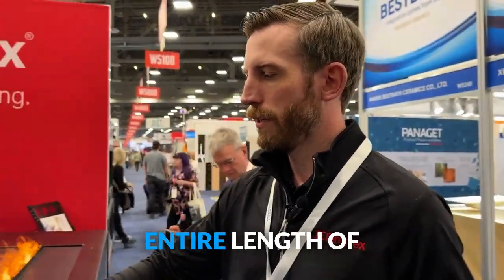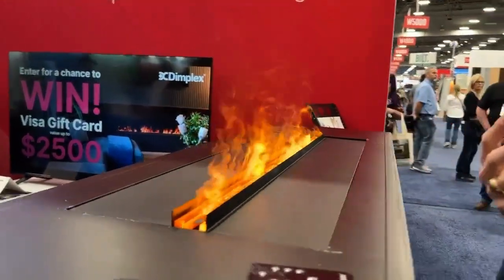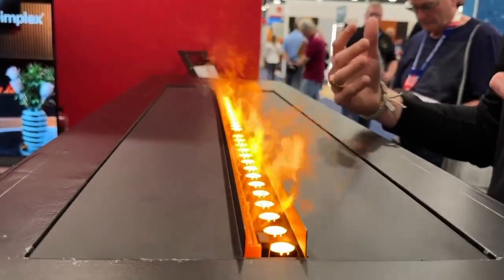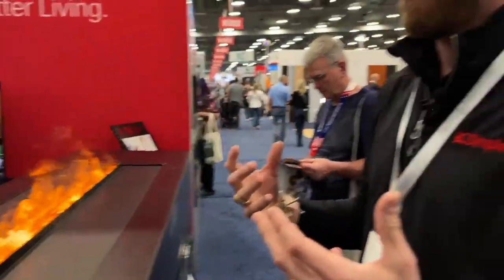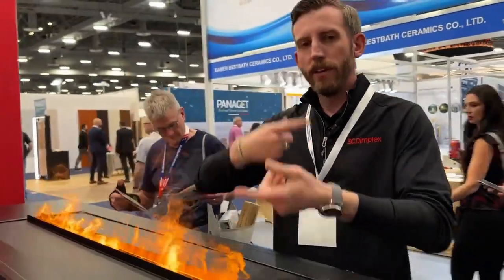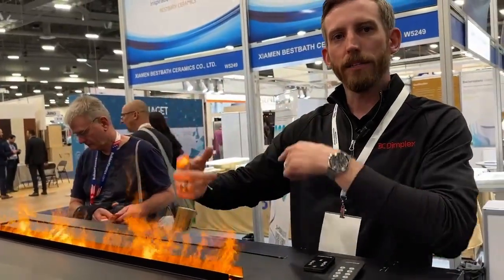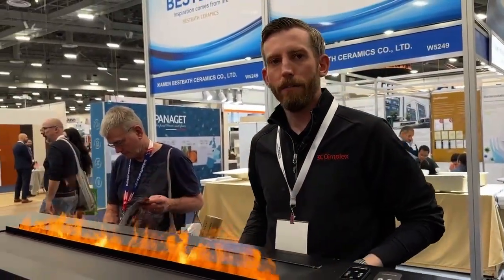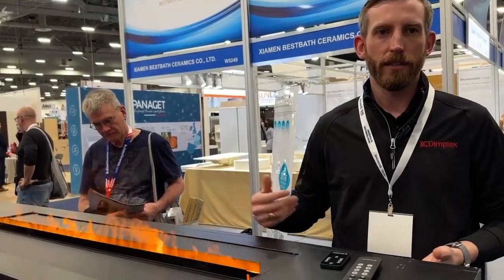All of our vapor products require intake air, so keep in mind how these function: there's a heater running across the entire length of the opening, and that heater creates an updraft for the vapor. We have a transducer producing the vapor, and out of these orange outlets is where it comes out, with the natural rise of the flame facilitated by the heater creating updraft. Once the heaters are warm, it creates a natural cycle of heat rising, and you need an opening to allow that heat or air to get to the bottom of the cassettes to facilitate that.